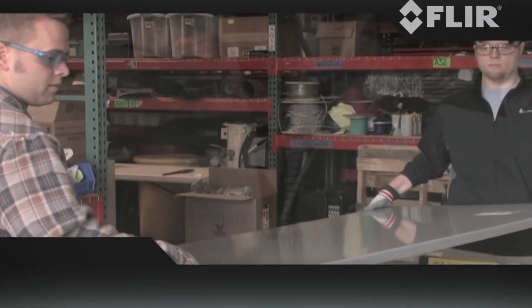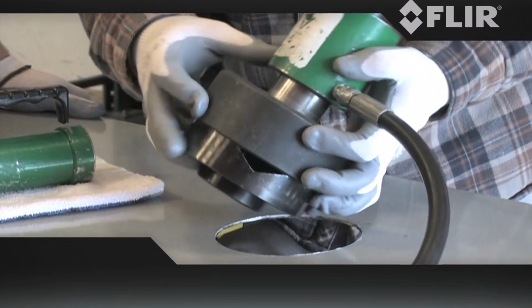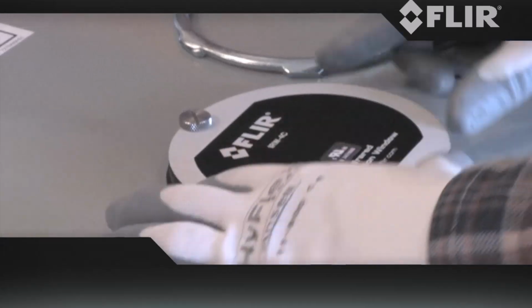Windows are installed over the fuses, breakers, bus, disconnects, and other components within the cabinet. Important to note for this application, there's not a lot of room between most panel covers and the electricity carrying components, so a wide-angle lens is most effective when using an infrared window. Let's take a look through an infrared window with our 24, 42, and 80 degree lenses.